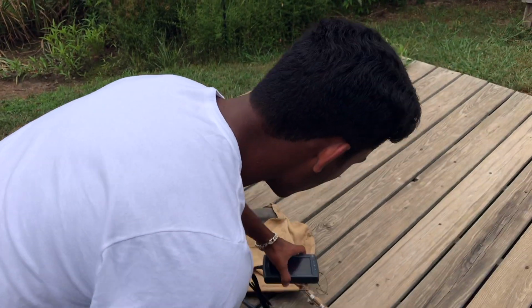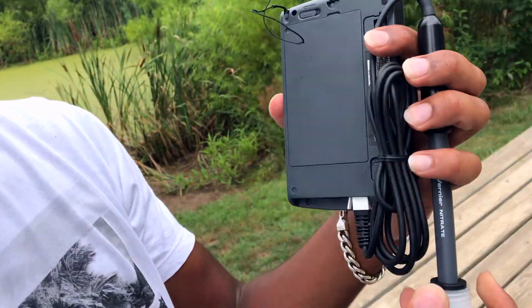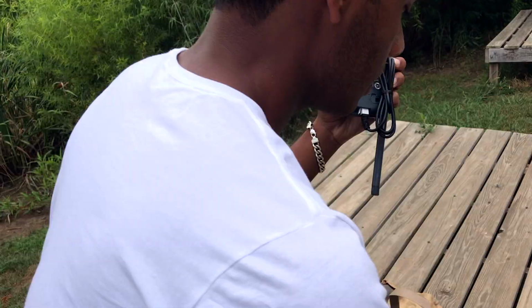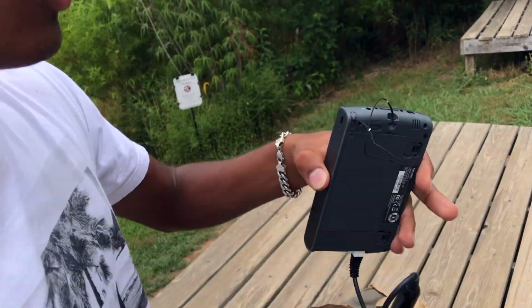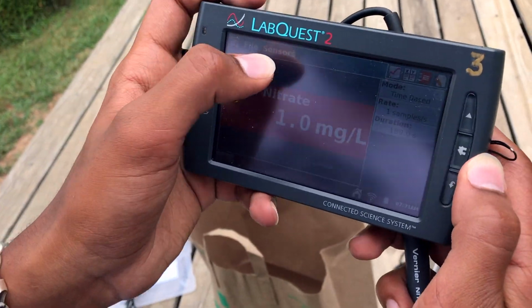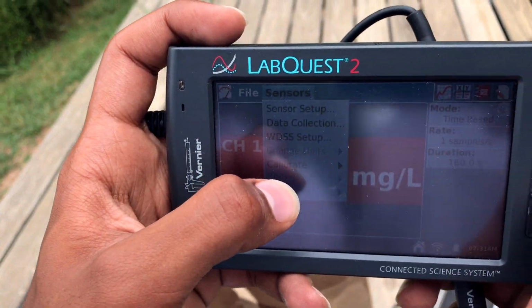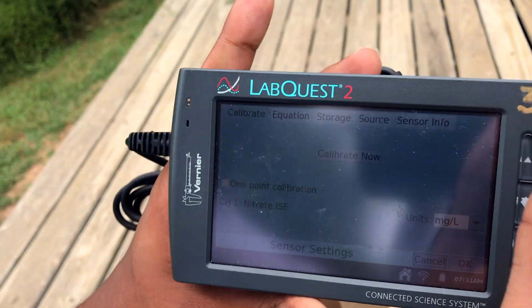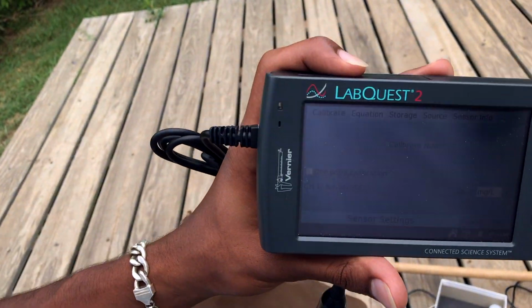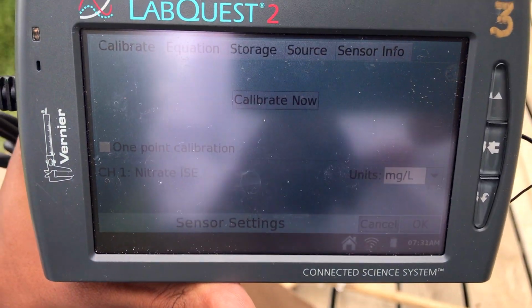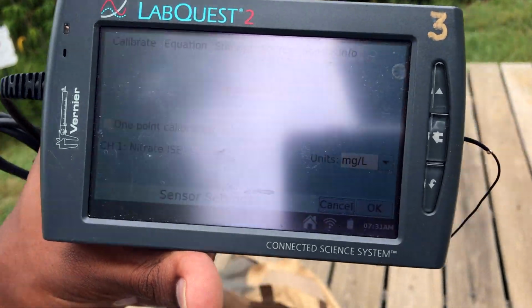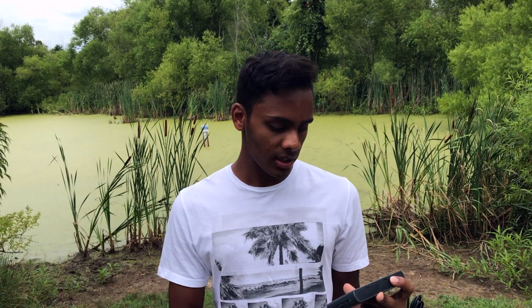What we do is we first take this out of its case, and then we go into sensors, calibrate. Under sensors and calibrate, you'll notice that there is 1-point calibration. I'm not sure if we can clearly see it on the video, but you will notice it on your LabQuest. 1-point calibration is usually used for the much simpler probes. But in this case, we're going to do a 2-point calibration since we do have two solutions provided. If you don't have two, you can go ahead with 1-point calibration and test your luck.